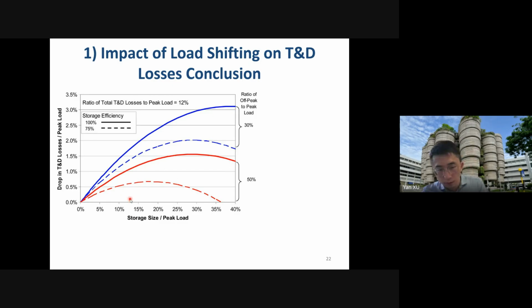Importantly, when the energy storage size is beyond a certain limit, the total drop starts to decline, especially for this curve, and the same for this one. The maximum point happens here for the blue dashed line, and here for the blue solid line. This is the peak value for the energy loss reduction—in other words, the best, optimal size of the energy storage. This is the first observation.